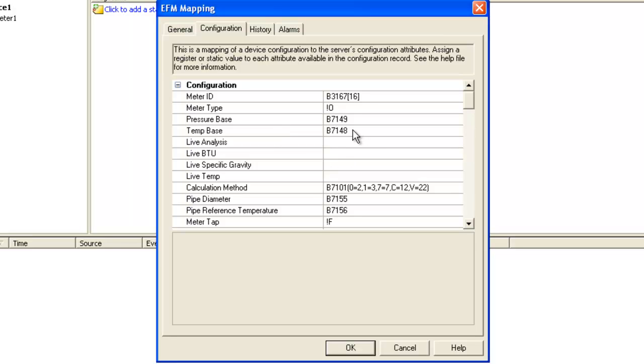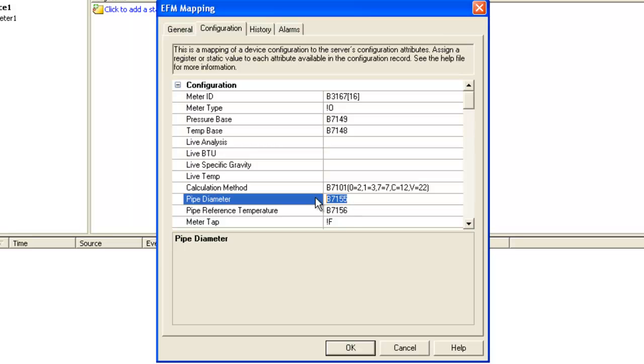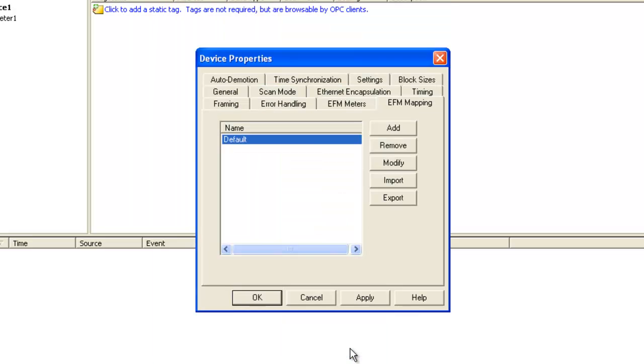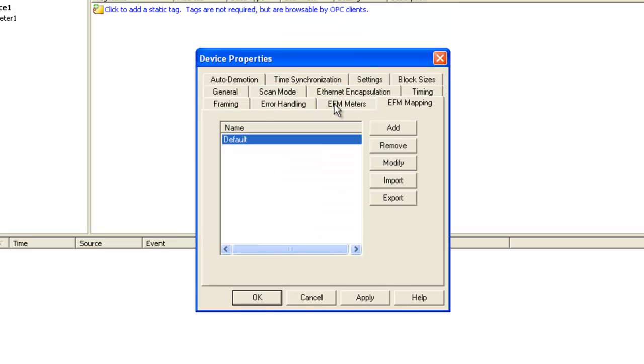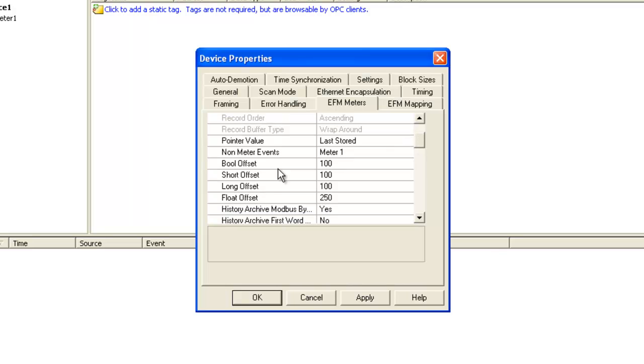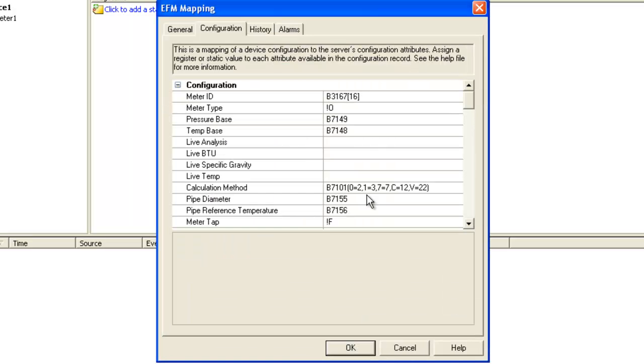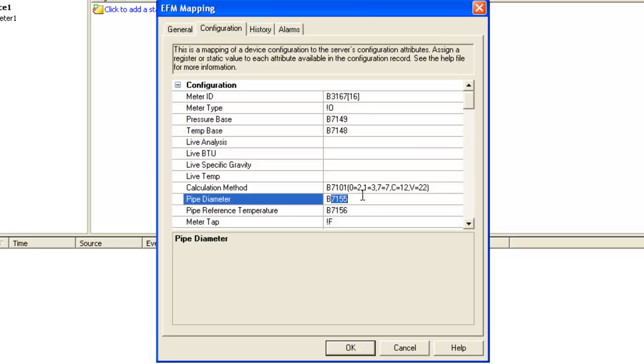So for configuration data, this represents the addresses we will read from the device on each poll. We support a base address syntax. So for example, if we look at pipe diameter, 7155 is a float address in Enron. So for meter 1, we'll read 7155. If we go back and look at our float offset, it's 250. That means that for meter 2, we'll read address 7155 plus 250, which is 7405.